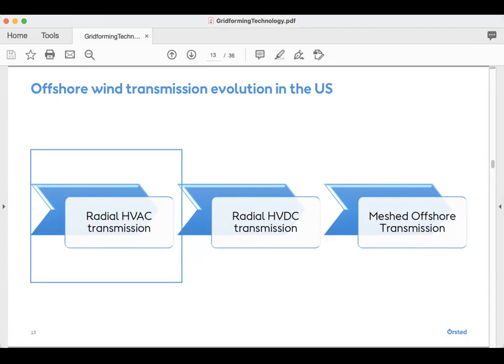That's when a lot of the offshore wind farms started looking at HVDC. Even then it was radial - most of the other generation projects coming up that include HVDC transmission are again looking at radial transmission, one wind farm connecting through an 1100 or 1200 megawatt HVDC system and coming onshore. Most of this HVDC system is monopole, symmetrical monopole. There were a few discussed at 400 kV symmetrical monopole, but most designs are 320 kV symmetrical monopole for most offshore wind projects, and all these are based on voltage source converter technology.